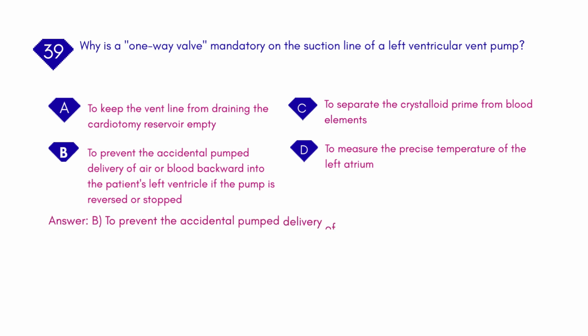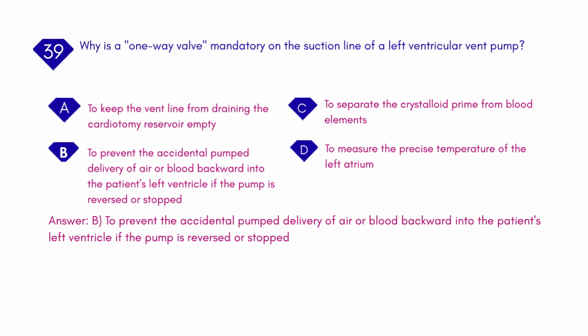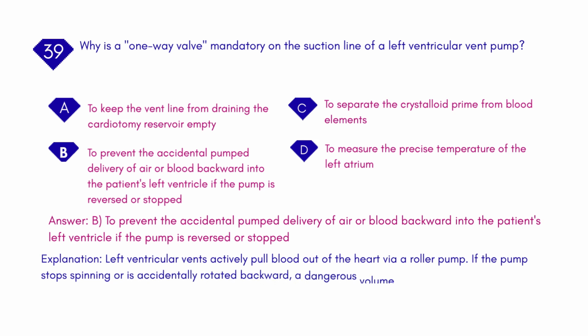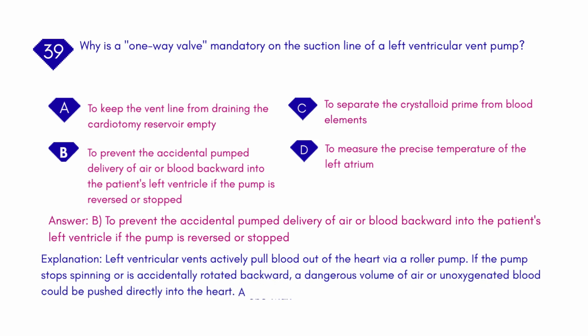Answer: B. To prevent the accidental pumped delivery of air or blood backward into the patient's left ventricle if the pump is reversed or stopped. Explanation: left ventricular vents actively pull blood out of the heart via a roller pump. If the pump stops spinning or is accidentally rotated backward, a dangerous volume of air or unoxygenated blood could be pushed directly into the heart. A one-way valve physically prevents any retrograde flow.